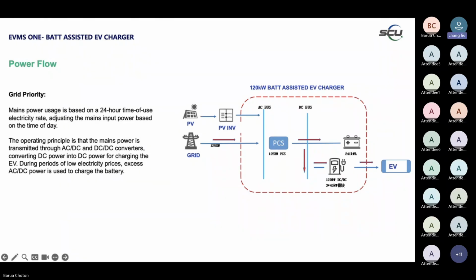What is the rating of the PV inverter? In this standard solution, you can use a maximum of 125 kilowatt of the inverter, because the PCS power is 125 kilowatt. The PV inverter is a separate device — I think I already answered this. Why is PV not directly connected to the DC bus? Because it's not MPPT. If it were MPPT, we could connect it straight to the DC bus.